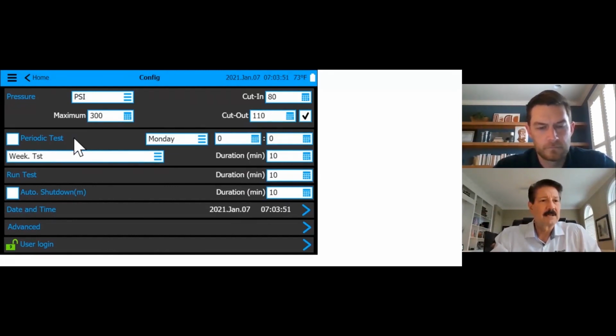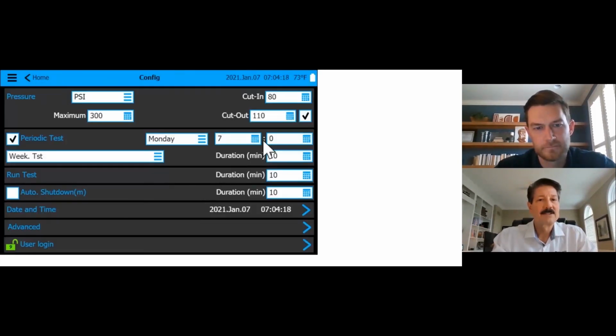Now we can do some periodic times. The code requires us to be able to have an automatic periodic test. Again, this is to meet NFPA 25 requirements. I can click this little box here. I can pick a Monday. I can pick it to start at 7 a.m. And the duration is going to be 10 minutes. It's going to be a weekly test on a particular day here.